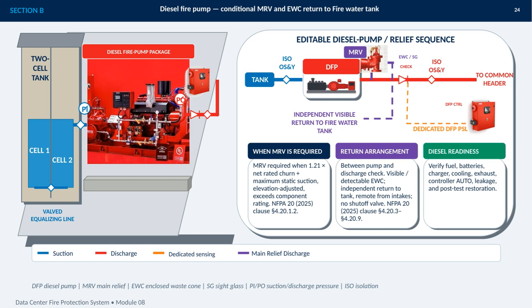When an MRV is required, its discharge is arranged between the pump and discharge check valve. The return must be visible or detectable through the EWC, independent, directed back to the firewater tank, remote from tank intakes, and installed without a shutoff valve. The final point is diesel readiness. Before and after testing, verify fuel, batteries, charger, cooling, exhaust, controller auto status, leakage, and complete restoration.